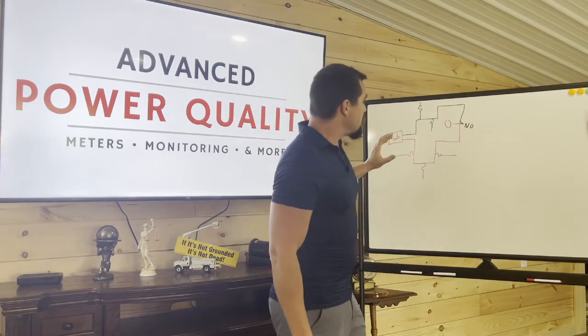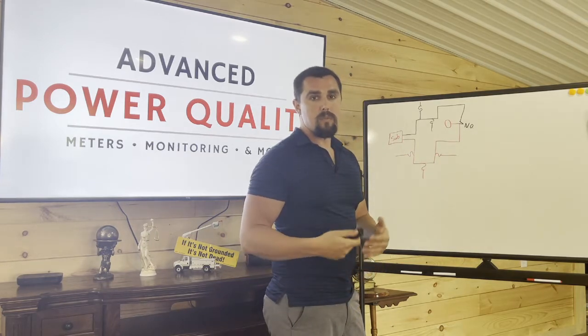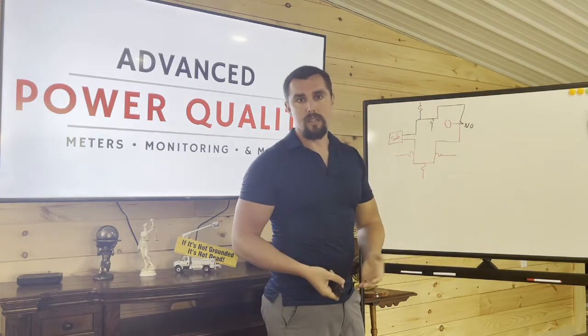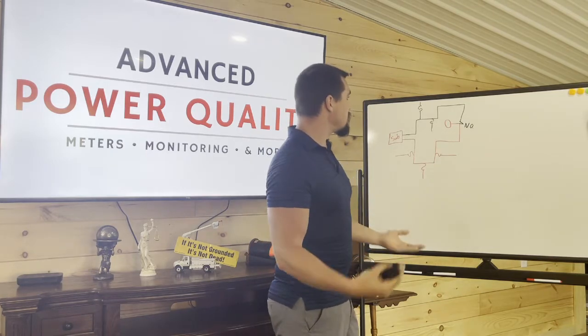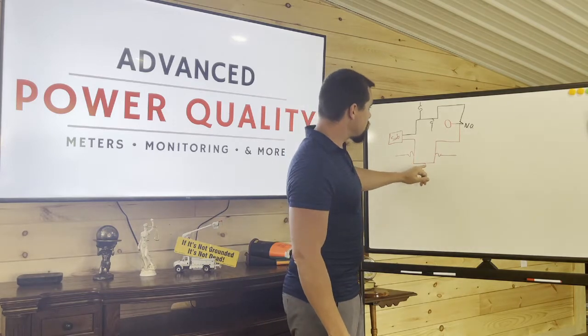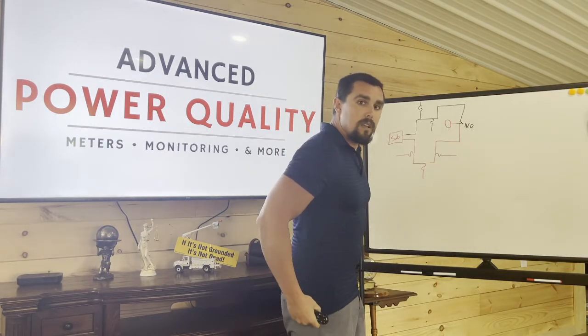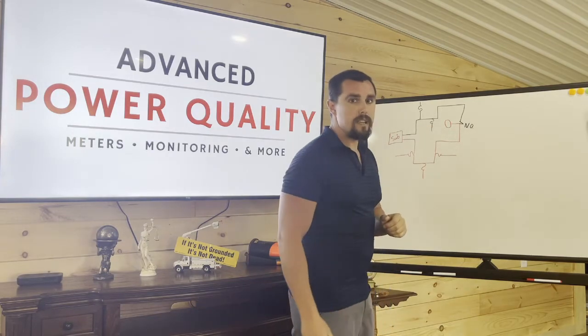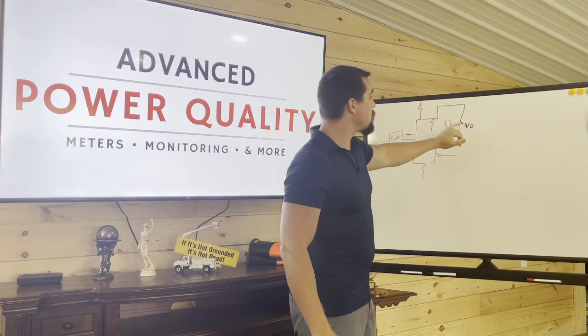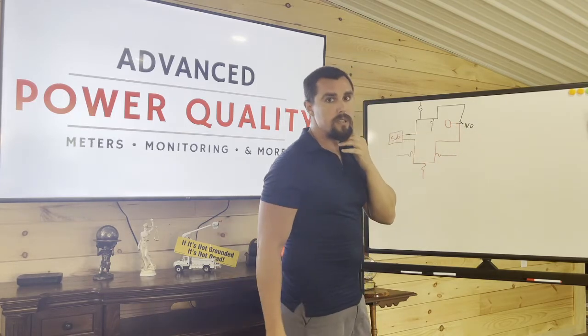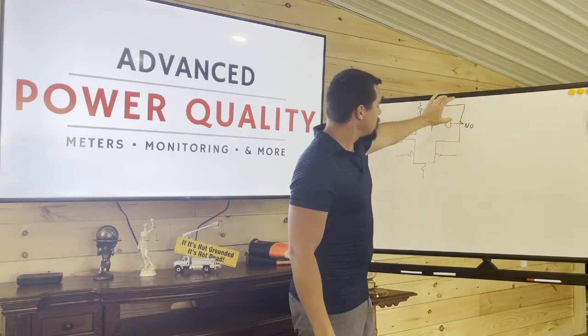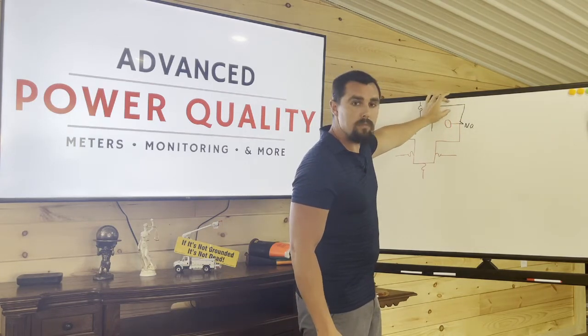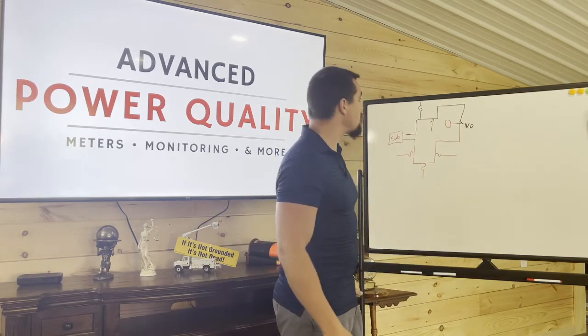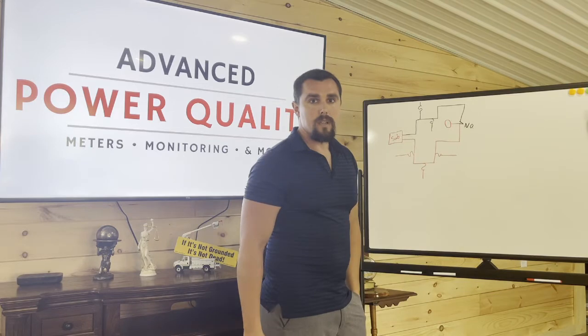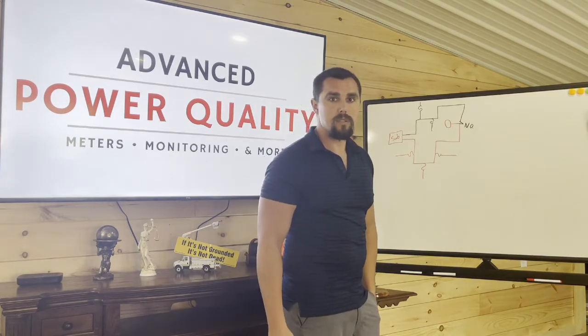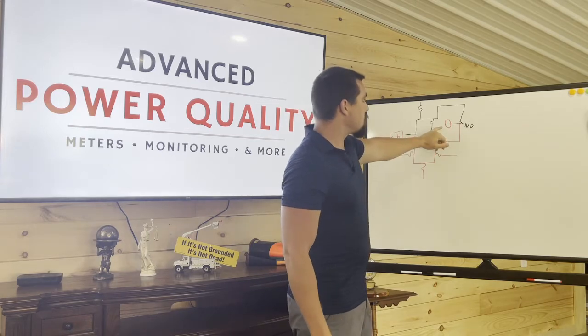So utilities have voltage controlling devices. One thing is a capacitor bank. I know this indirectly affects voltage, it's essentially VAR control, but it does affect voltage. So let's say red feed has 2 or 3 capacitor banks on it, okay? Let's say black feed doesn't have any, and at the end of the line, no regulator banks, no nothing. At the end of the line, you have a lower voltage here. So storm happens, the utility needs to switch this customer to black feed to restore as many customers as possible. Well, this can run into some voltage concerns for our customer, and they're wondering why they're having voltage concerns. So that is an item to look for.